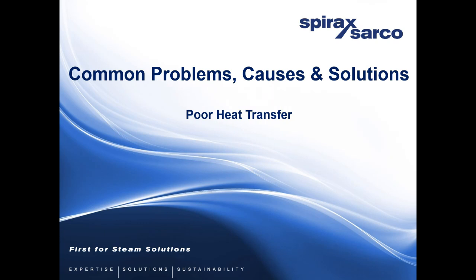Temperature is another one. By checking the temperature of the trap, tying the temperature up to the pressure of the line, you can tell whether the trap is working properly. When we speak of, say, a 180 degree steam system, it's not completely steam. At 180 degrees, you can have both water and steam. So the trap should be at the corresponding temperature for your line. If it's hotter, at steam temperature, it gives you an indication it's leaking. If it's colder than your condensate system, you can tell it's probably failed closed.